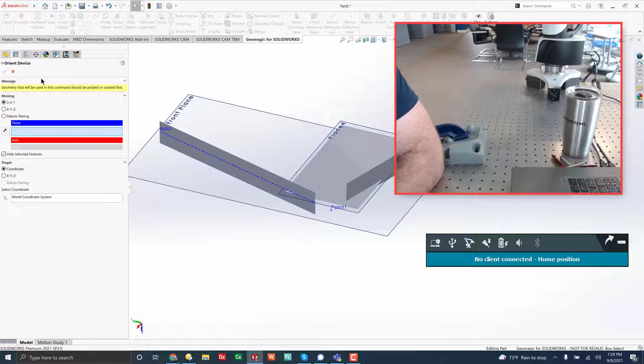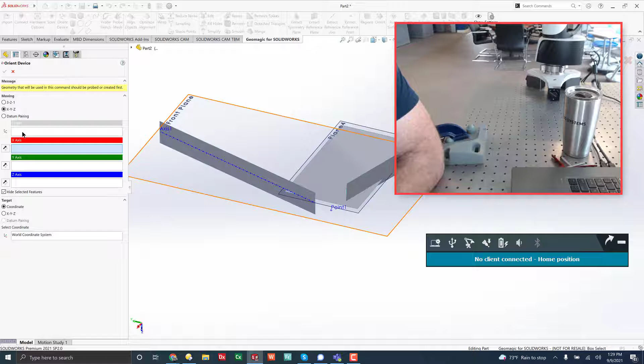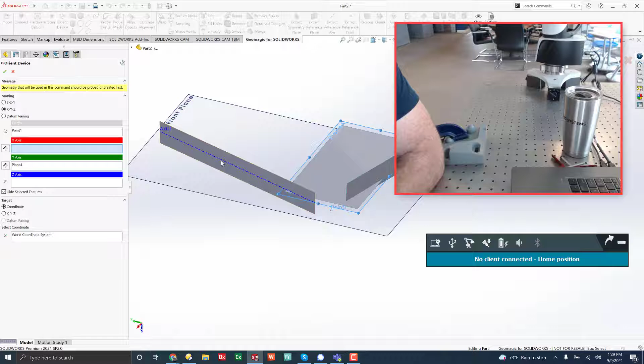So I went ahead and created a point. Now if I come over to the plugin and go to Orient Device, I like to use XYZ. 3-2-1 is like a plane, line, point alignment. XYZ breaks out the origin with the directions. So the 6 degrees of freedom, the 3 positional are covered under the origin selection, and then the 3 rotational are covered under these dialog boxes. So the way this works is I can set that point as my 0, and then if I want this plane to be Y up, I can make that. And then if I want this vector to be my x-axis, I can set that and then hit Orient Device.